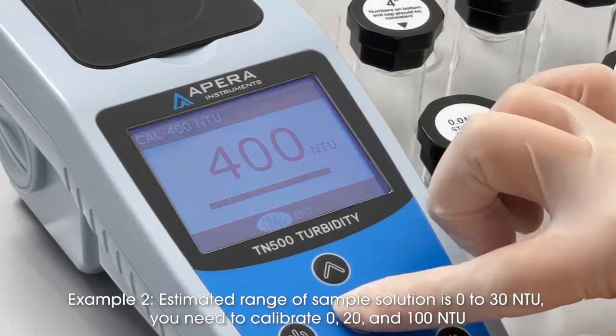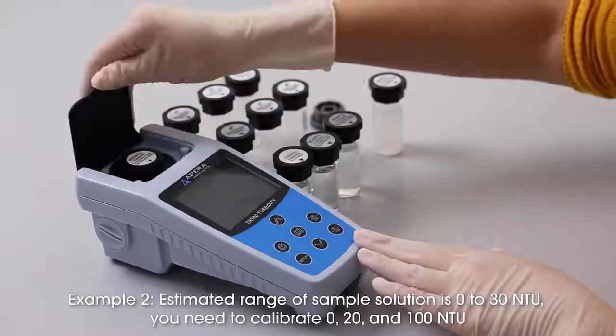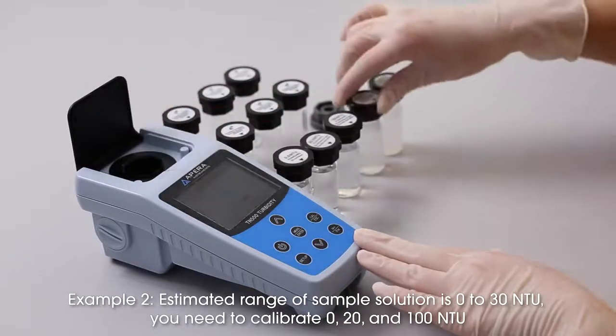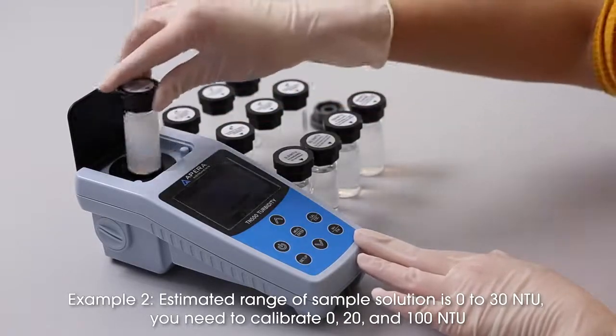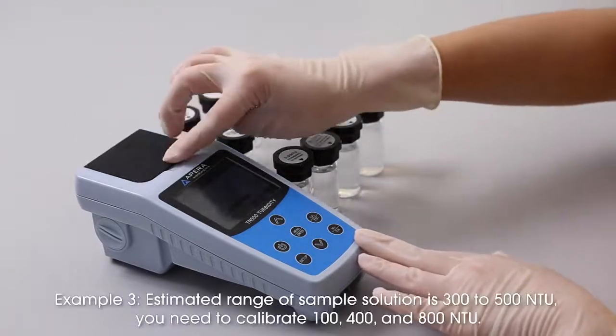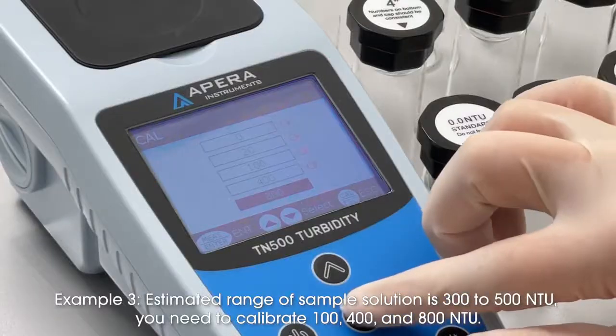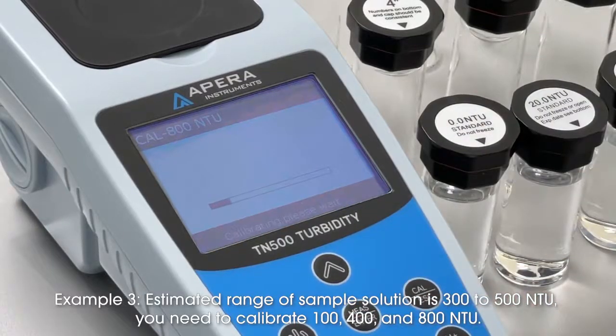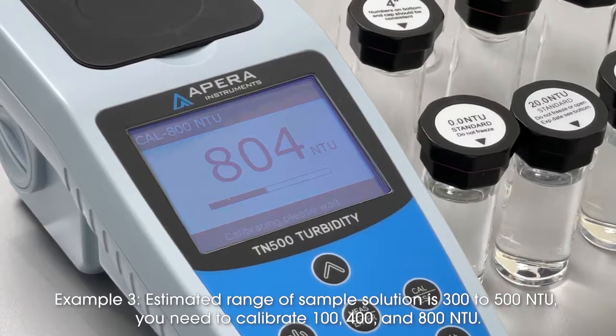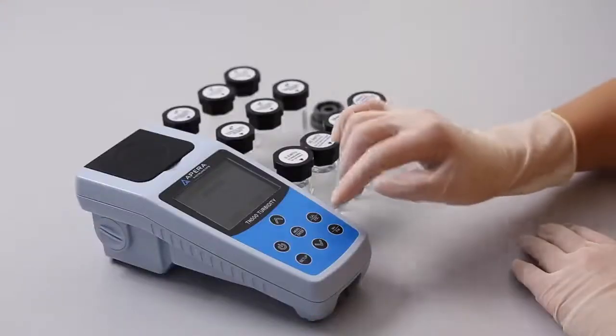Example 2. Estimated range of sample solution is 0 to 30 NTU. You need to calibrate 0, 20, and 100 NTU. Example 3. Estimated range of sample solution is 300 to 500 NTU. You need to calibrate 100, 400, and 800 NTU.